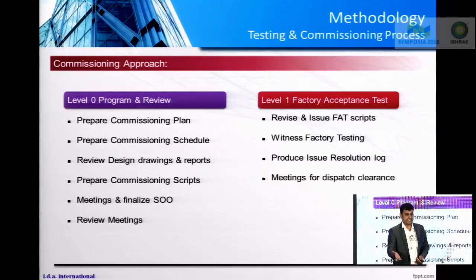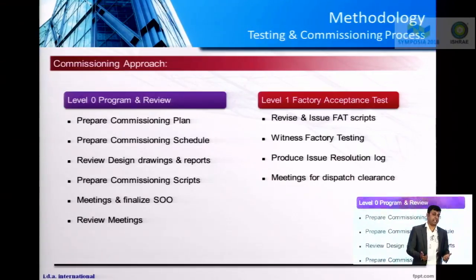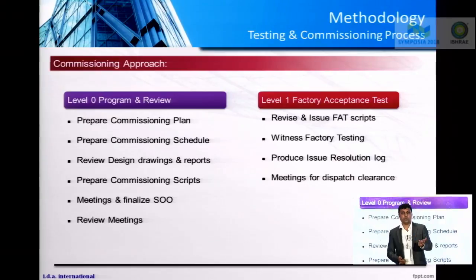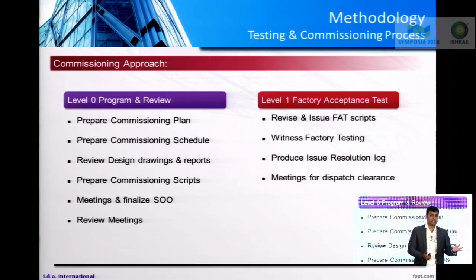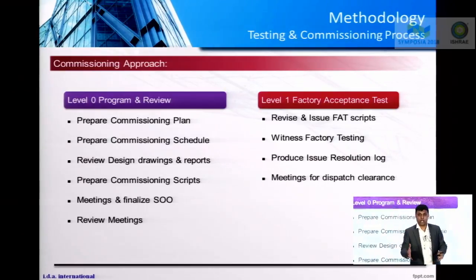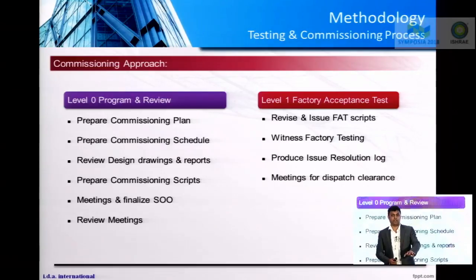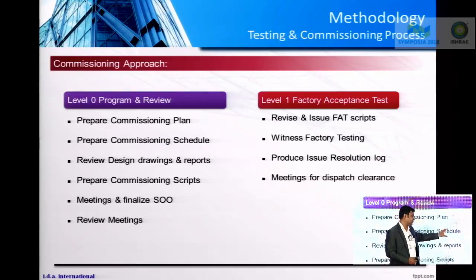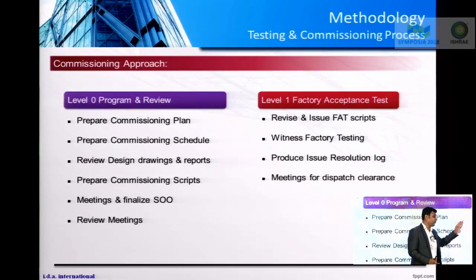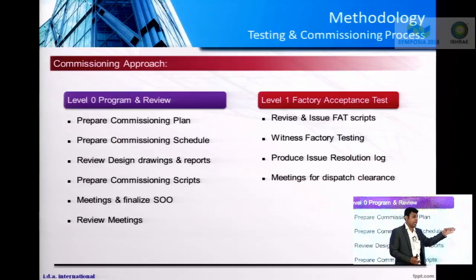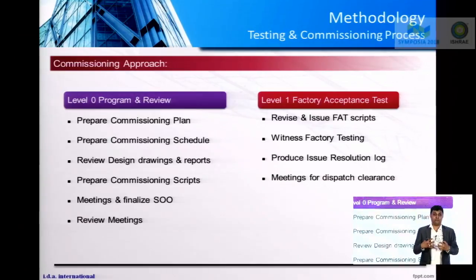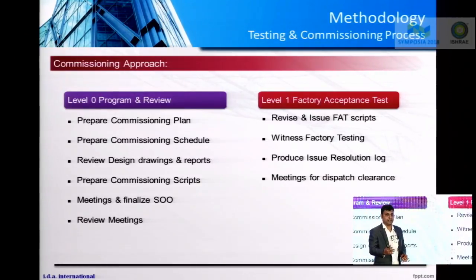The moment you're out of design, the moment you're into the construction stage, there are some critical equipments for which we have to go for a factory acceptance test. Now, what are those critical equipments? Those are chillers, PDUs, UPS, precision air conditioning units, switch gears, HT switch gears, transformers, etc. So all these critical equipments, we have to verify their performance at the very beginning through a factory acceptance test. The job of the commissioning team is to ensure they produce the right scripts, they witness the test, they issue reports, and they have the authority to provide dispatch clearance for the equipments. Only when they're satisfied with the performance of the equipment do they have the right to provide dispatch clearance. So that's level 1.